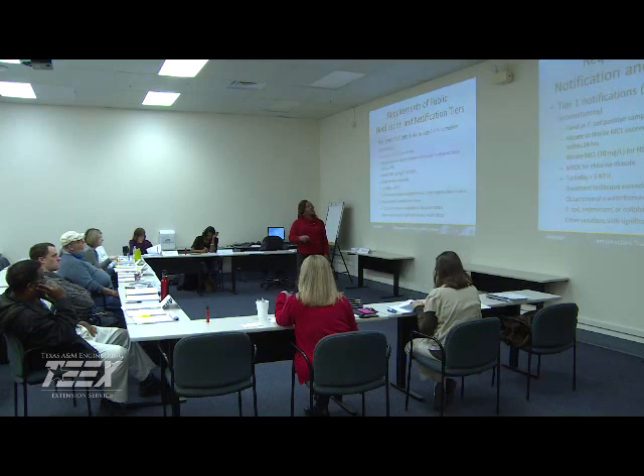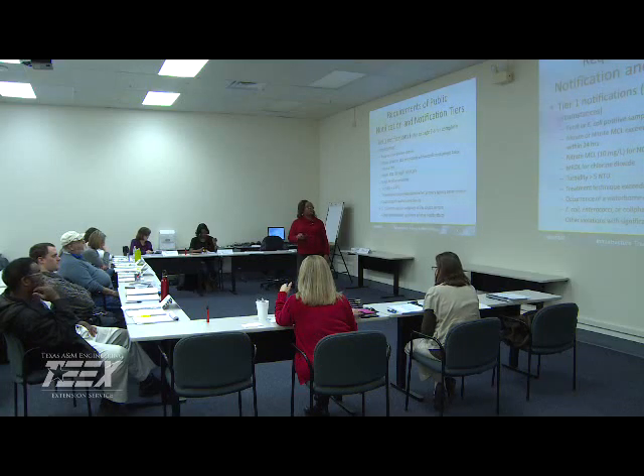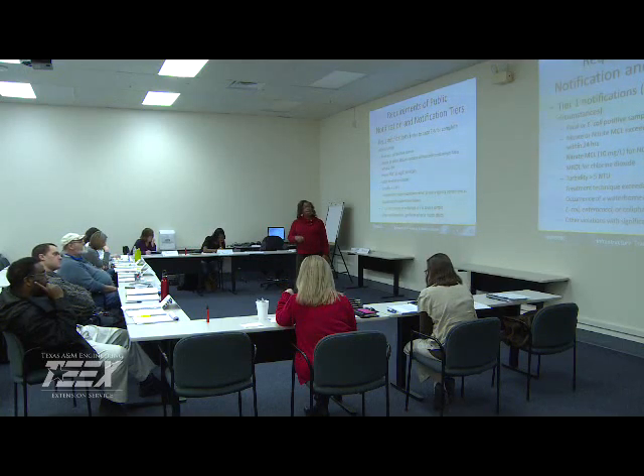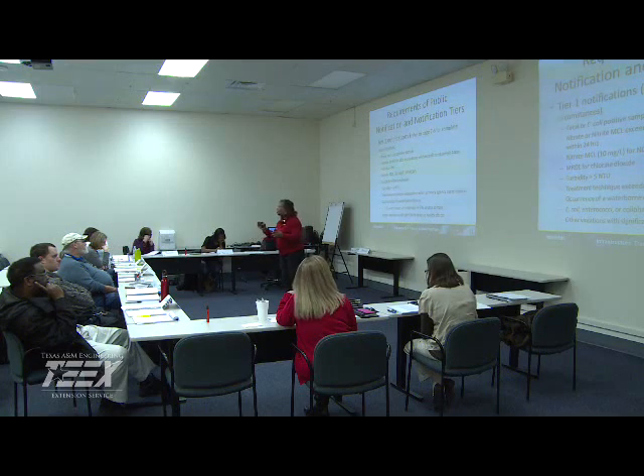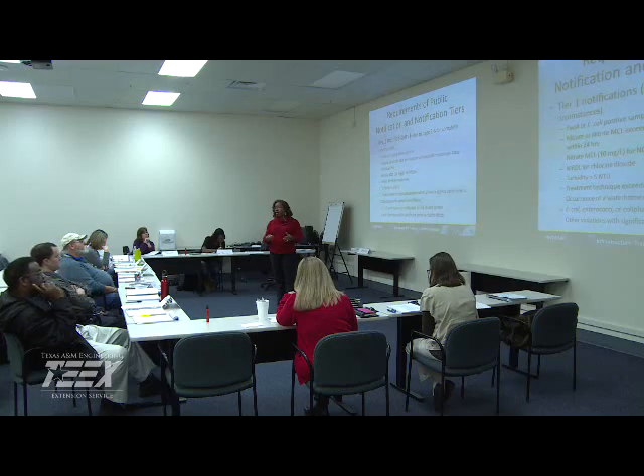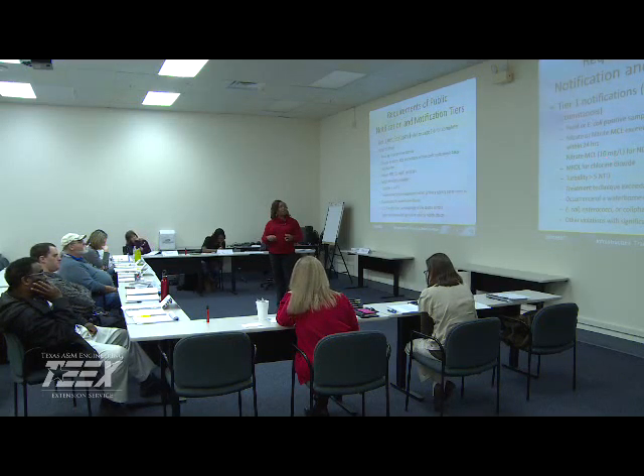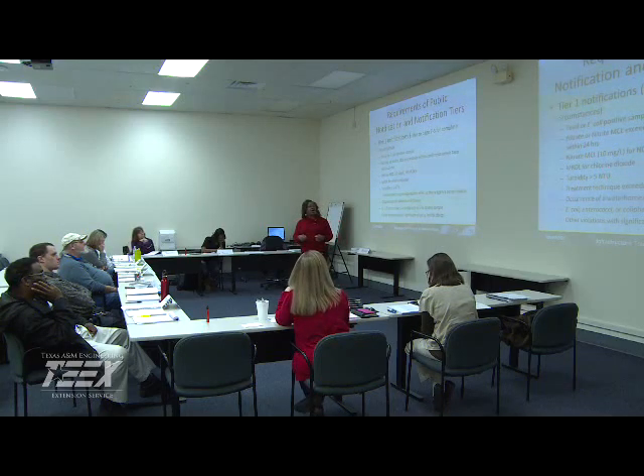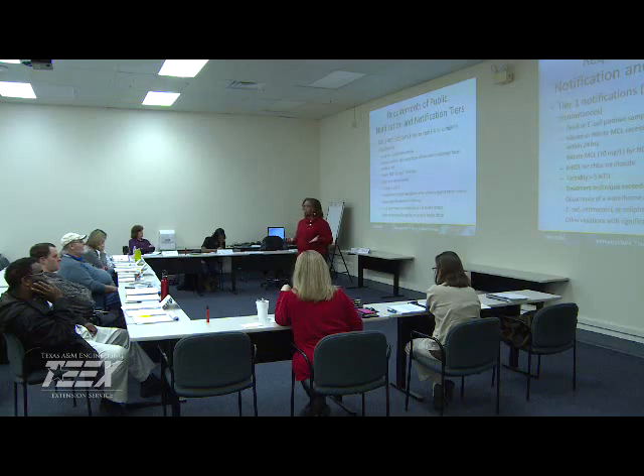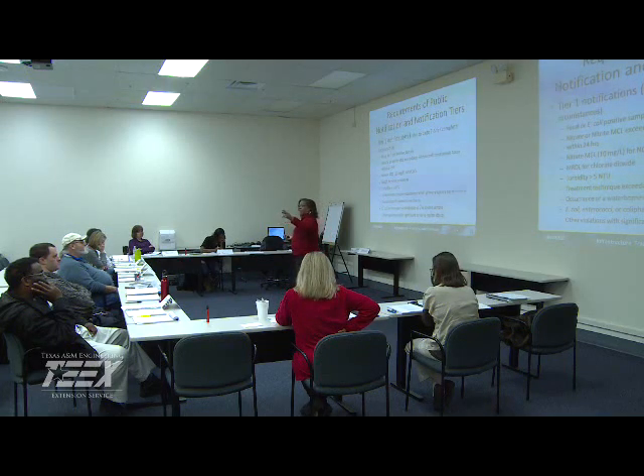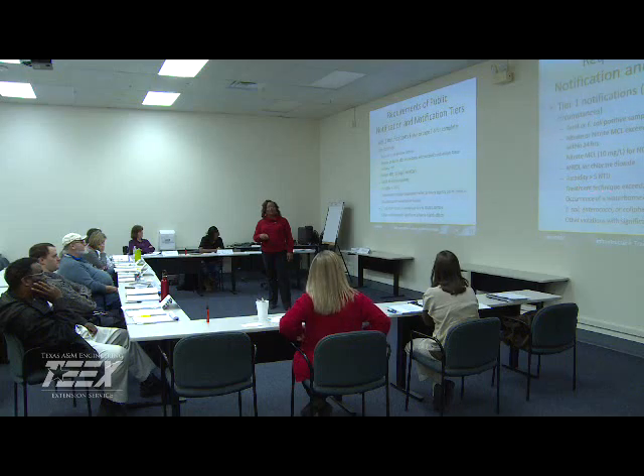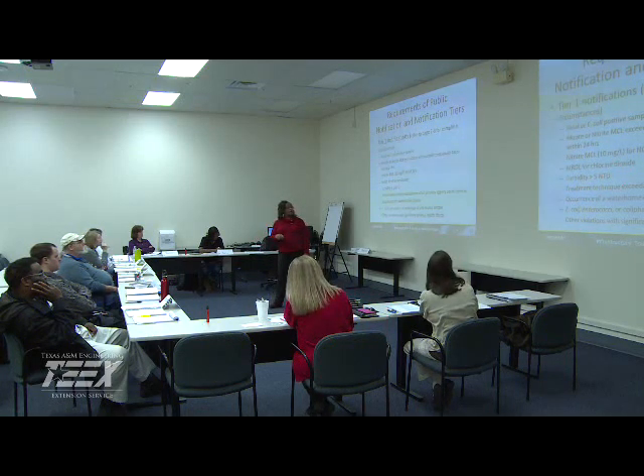What constitutes a Tier 1 notification? You can refer to page 76 for the complete listing. Any time you have a fecal coliform or E. coli positive — acute. Any time you have a nitrate or nitrite with a confirmed positive within 24 hours — acute. Exceedances of nitrate above the maximum contaminant level for your non-community water system — acute. The MRDL for chlorine dioxide — acute. What do we use chlorine dioxide for? Disinfection — though fortunately no systems in Delaware use it.